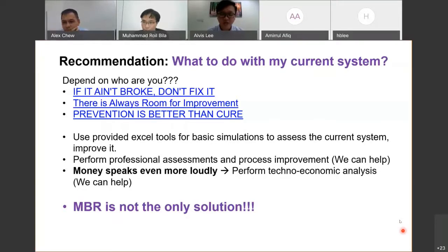So for the last question: is it suitable to use MBR if normally the sludge is floating after chemical and physical treatment? Well, this is the advantage of MBR. You cannot do it for activated sludge, but yes, you can do it for MBR because we don't care about the state of the sludge. As long as it is a microorganism, it will be separated by the membrane.